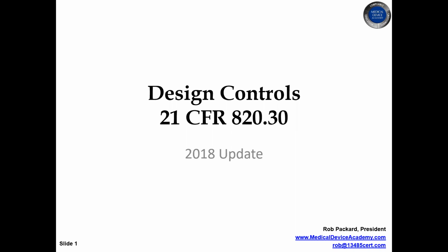Today's webinar is on design controls. The FDA regulation for this is 21 CFR 820.30, that's a subsection, .30. And it also is the same requirement for ISO 13485:2016, clause 7.3. This is the 2018 update, and I've recorded it.